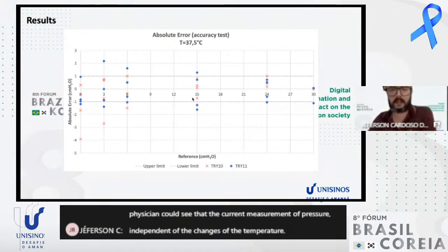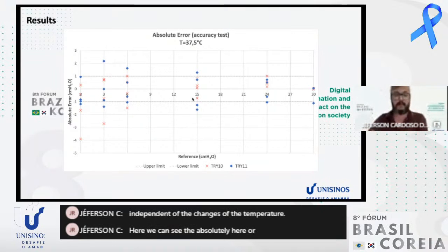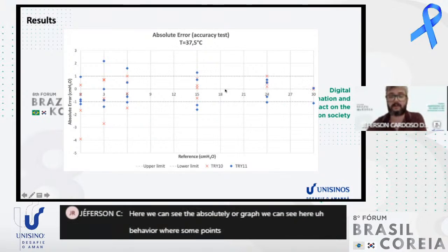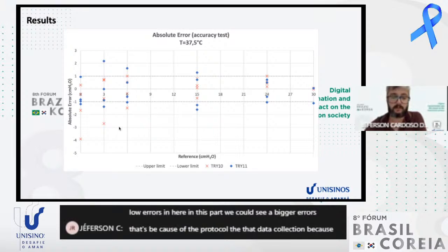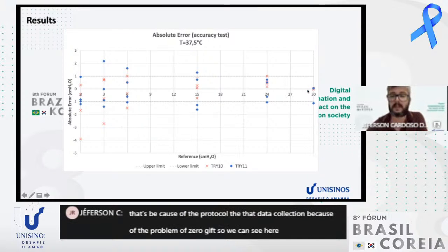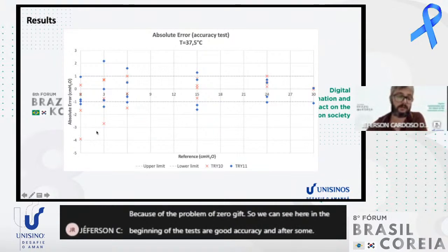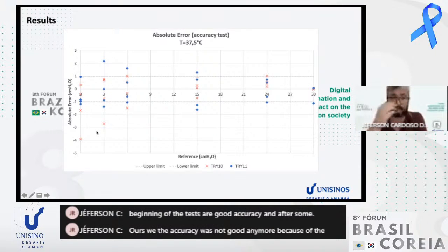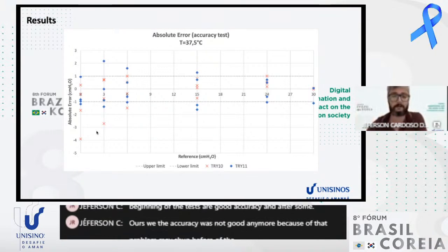Here we can see the absolute error graph. We can see behavior where some points are very close, with very low errors, and here in this part we could see bigger errors. That's because of the protocol of the data collection, due to the problem of the zero drift. So we can see in the beginning of the test a good accuracy, and after some hours the accuracy was not good anymore because of that zero drift problem mentioned before.